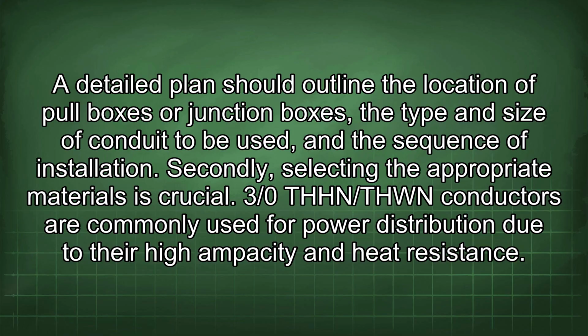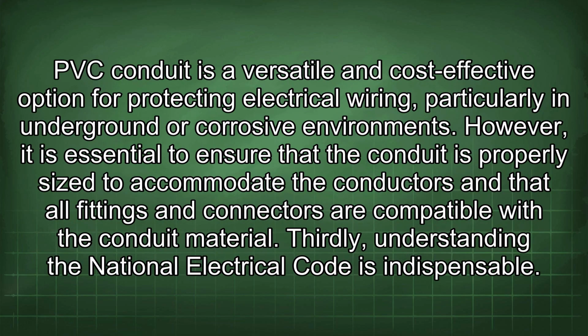Secondly, selecting the appropriate materials is crucial. 3/0 THHN/THWN conductors are commonly used for power distribution due to their high ampacity and heat resistance. PVC conduit is a versatile and cost-effective option for protecting electrical wiring, particularly in underground or corrosive environments. However, it is essential to ensure that the conduit is properly sized to accommodate the conductors and that all fittings and connectors are compatible with the conduit material.